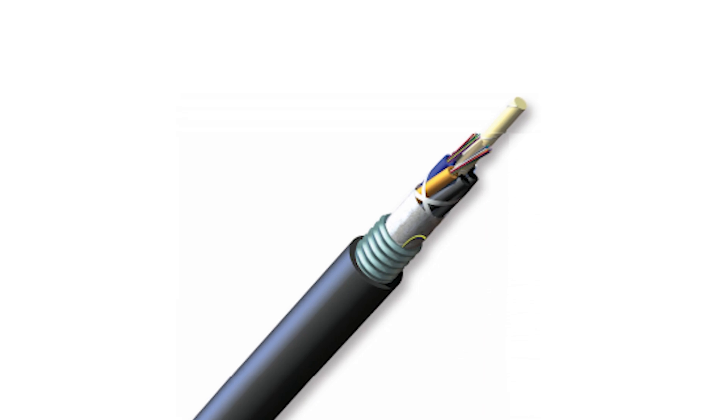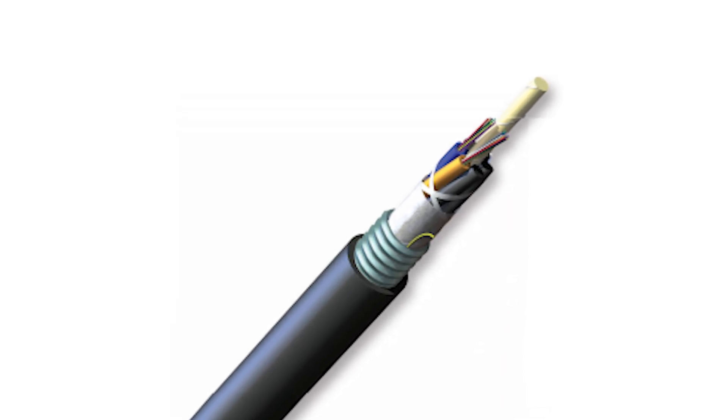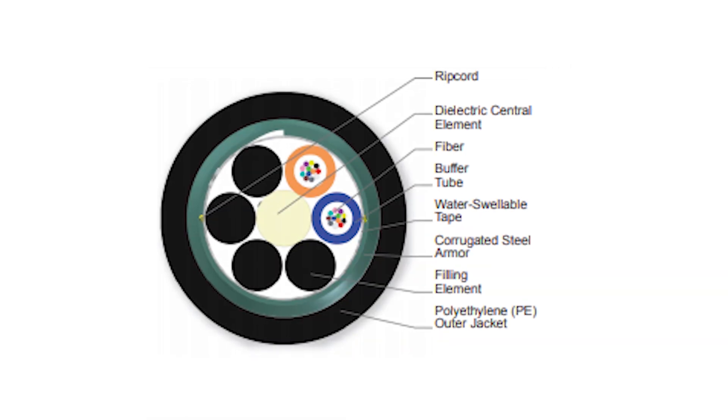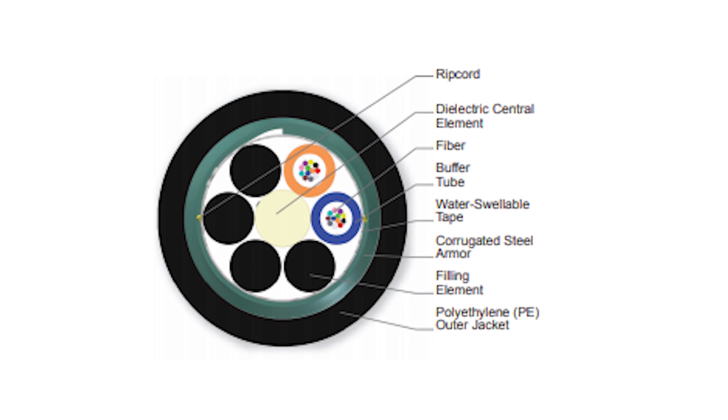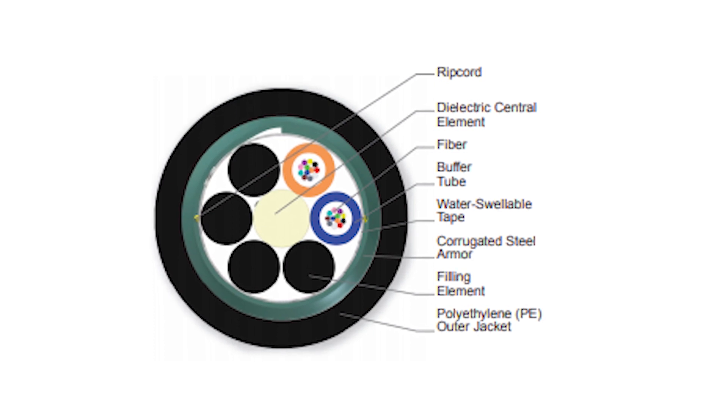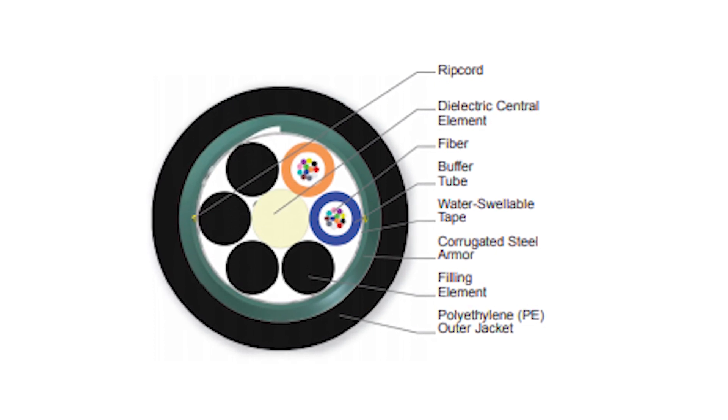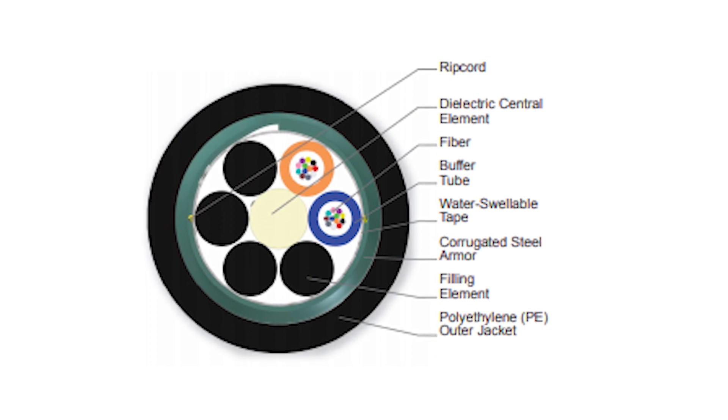This assembly is made with a heavy-duty polyethylene jacket and corrugated steel armor construction which provides crush and rodent protection. Its inner construction consists of a ripcord dielectric central element, the fiber, a buffer tube, water swellable tape, corrugated steel armor, and filling elements.